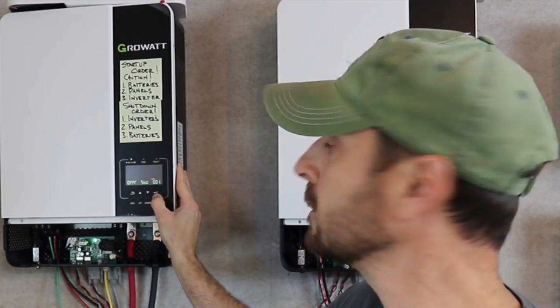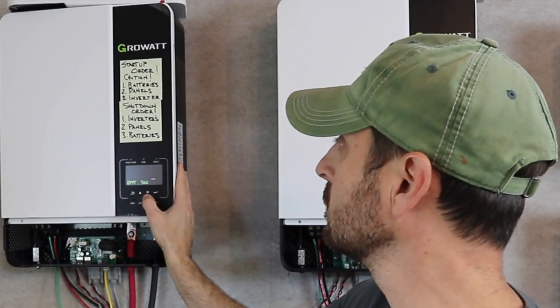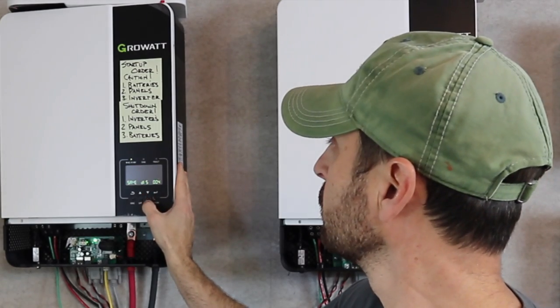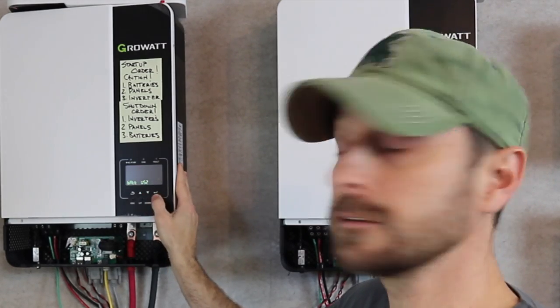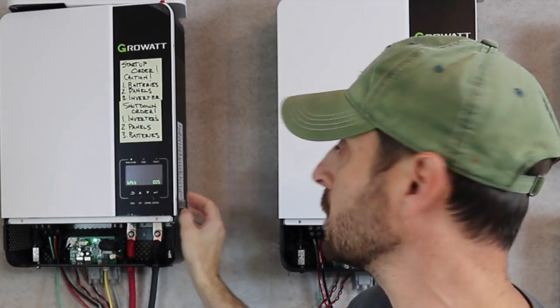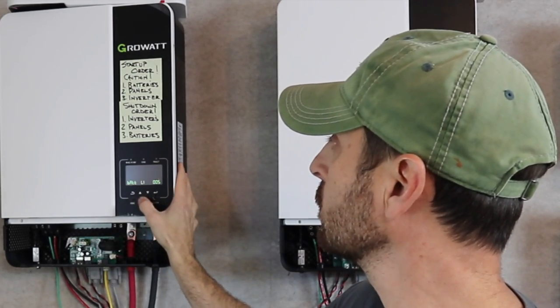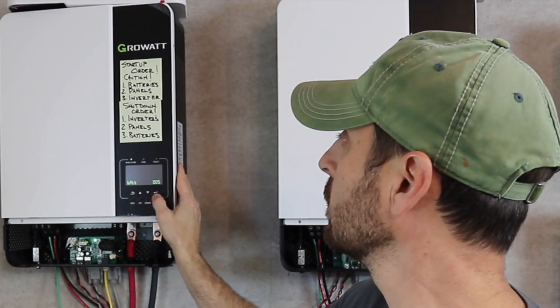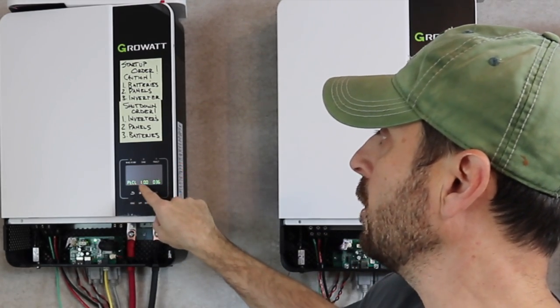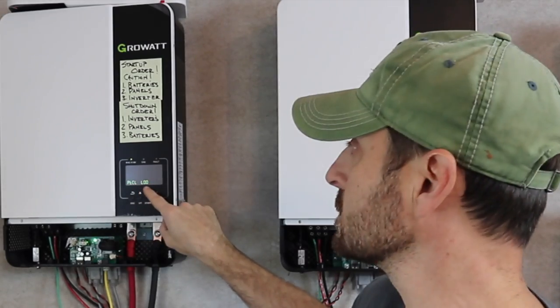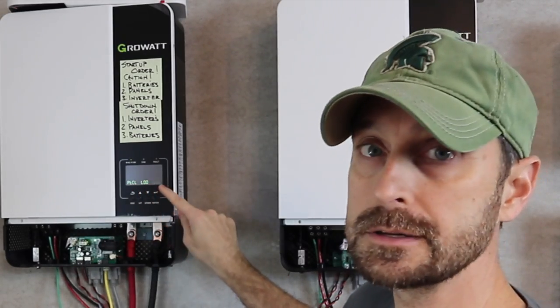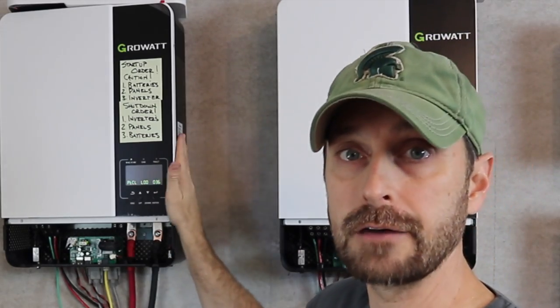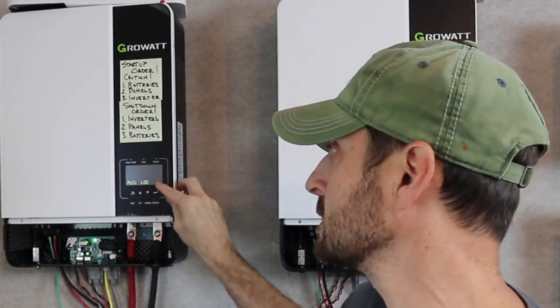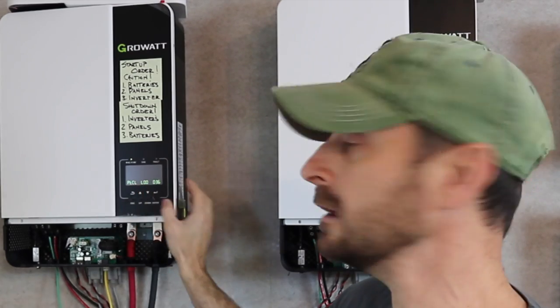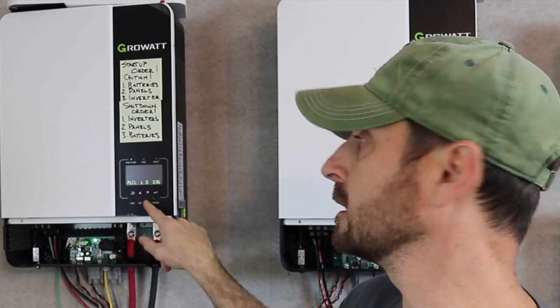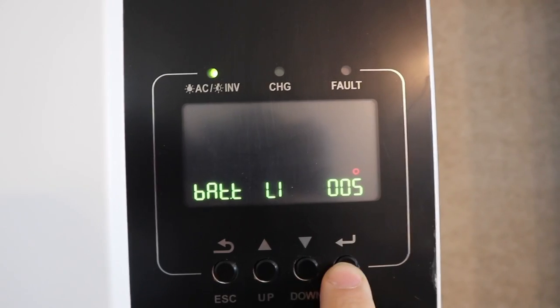So we're gonna hold down enter. We're gonna cycle down to setting 5. Enter to get into it. You see it said US2 to start. And we're gonna scroll down to LI. We're gonna enter and it's gonna give me L00 right in the center, and protocol 36. 36 is correct for the 5K inverters. The other inverters have different numbers on this side. So I need to scroll over to here by hitting enter, and then we're gonna set it at L01.